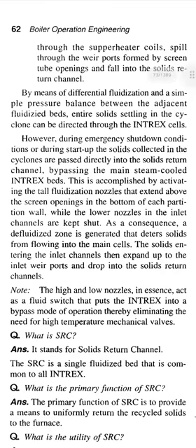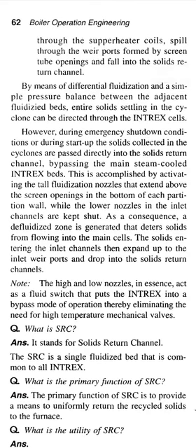However, during emergency shutdown conditions or during startup, the solids collected in the cyclones are passed directly into the solid return channel, bypassing the main steam cooled Intrex beds. This is accomplished by activating the tall fluidization nozzles that extend above the screen openings in the bottom of each partition wall, while the lower nozzles in the inlet channels are kept shut.